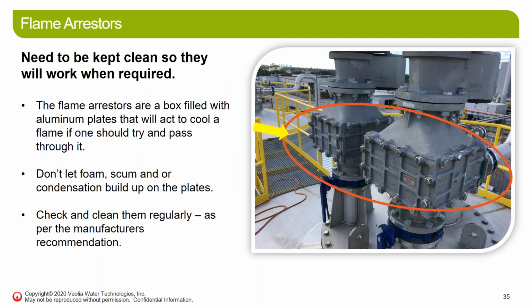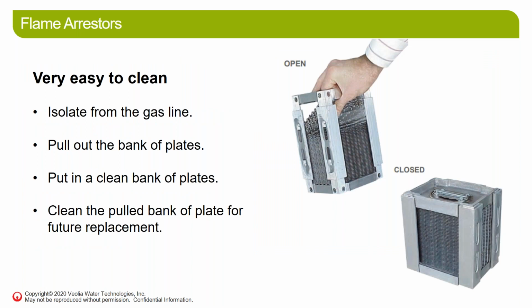Flame arresters are, again, like a backflash preventer, so they need to be kept clean. Don't let foam or scum or anything get up in them. Check them regularly. Just as a note, if you have these flame arresters and PRVs in a cold climate, make sure they're heat traced and insulated, because condensation building up in there can cause freezing, and then your pressure relief valve isn't working if those things are frozen. So check those and clean them regularly. They're pretty easy to clean.